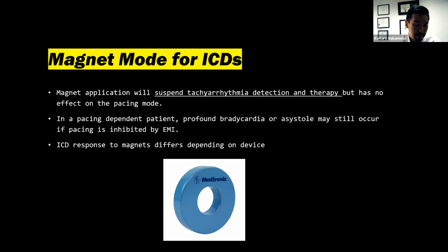For ICDs, it's different, which is why in the beginning we talked about being cognizant of whether your patient has an ICD or a pacemaker. Magnet application on an ICD will suspend tachyarrhythmia detection and therapy, but has no effect on the pacing mode. Suspending detection and therapy is important because EMI could be misinterpreted as a tachyarrhythmia and the ICD could deliver a shock. But as you know, ICDs have pacemaker function, and the magnet will not affect the pacing mode.